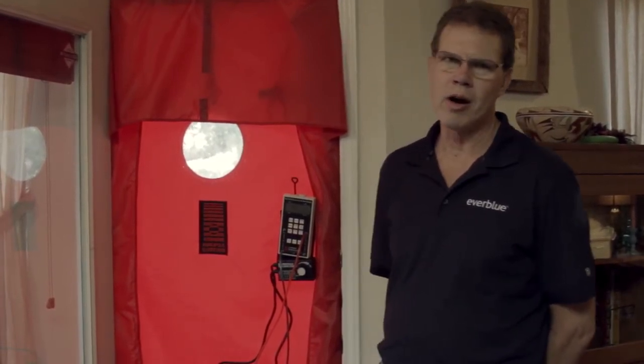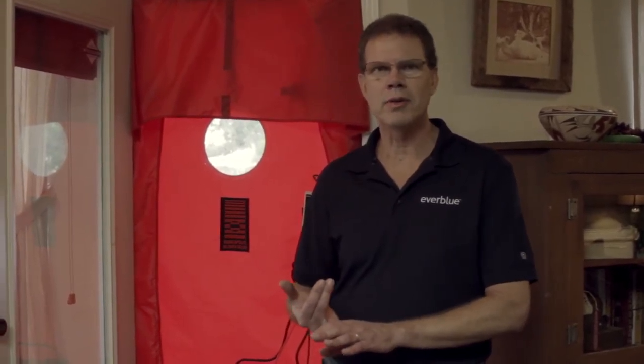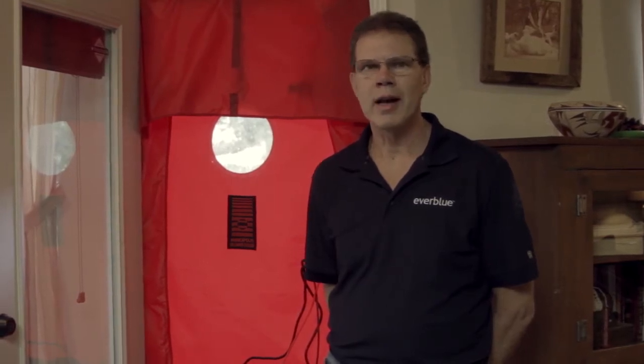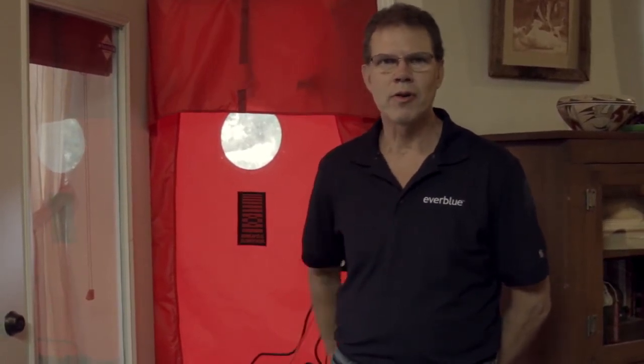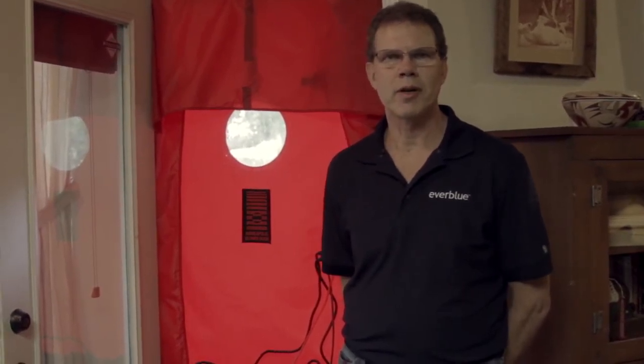We're interested in air changes per hour for a couple of reasons. One is we want to make sure that the house is not either too leaky or too tight. If it's too tight, you could have condensation and water vapor issues. If it's too leaky, obviously, it's a drain on your energy bills. So we've taken measurements of the house, we'll establish what the volume is, plug it into a formula, and find out what our blower door reading should be against what our blower door reading actually is. We'll compare the two, and then we can make recommendations to Betty as far as any changes she may want to make to the house.